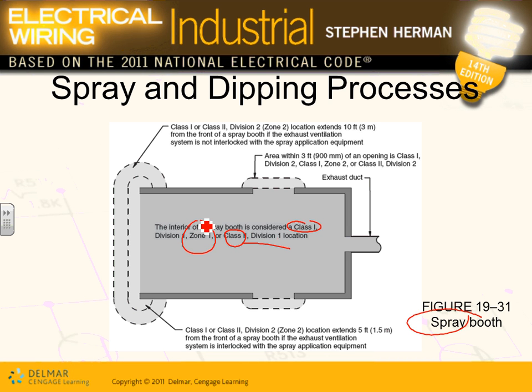The other one. And look at this one. This area, guys, is a class 1 div 2 around the opening, around 3 feet from every opening. Look at this one also, class 1 or class 2 div 2. They get you all around the openings. Can you see that? They want you to clear all these openings up to 10 feet. Any opening is classified as class 1 div 2. Inside is class 1 div 1. Does that make sense? Up to 3 feet, in this case up to 5 feet here.